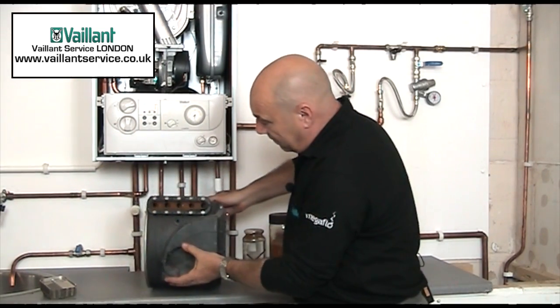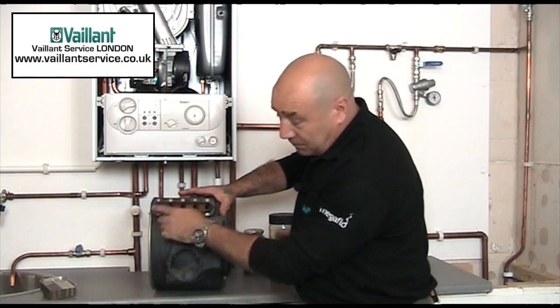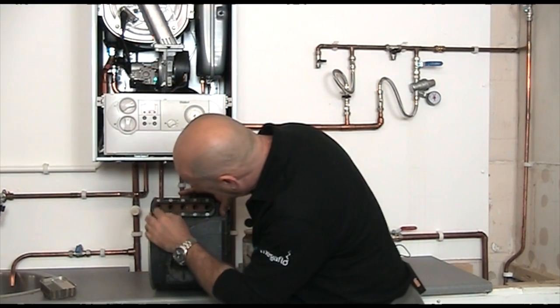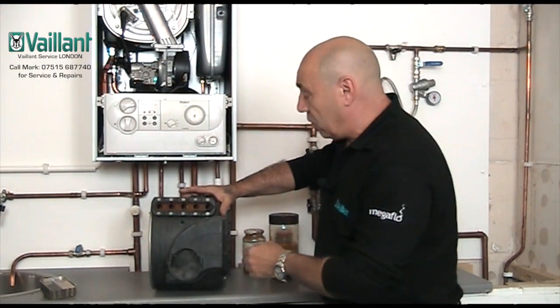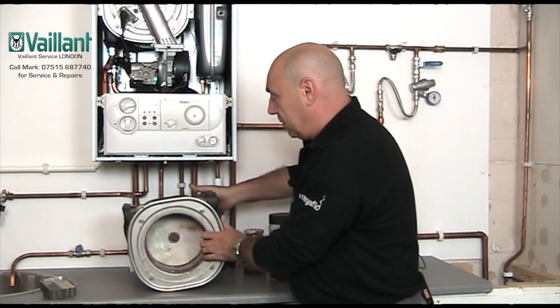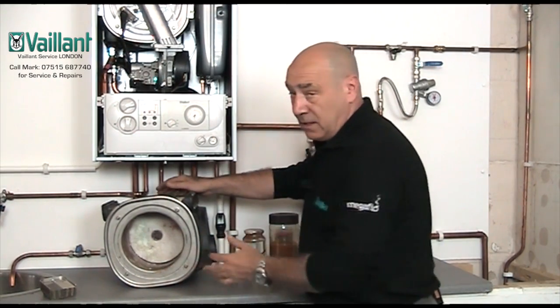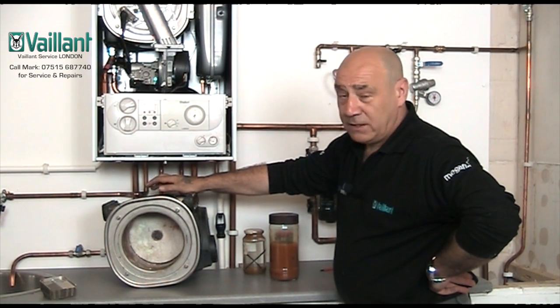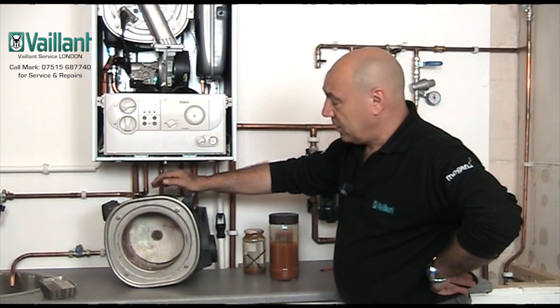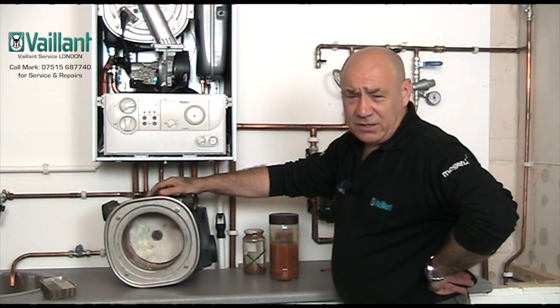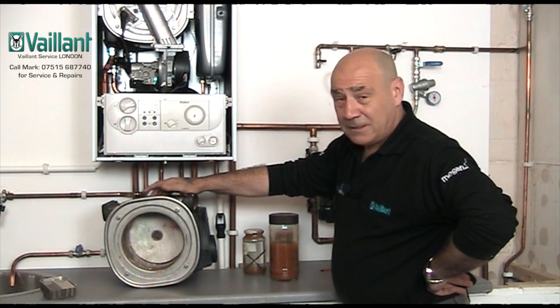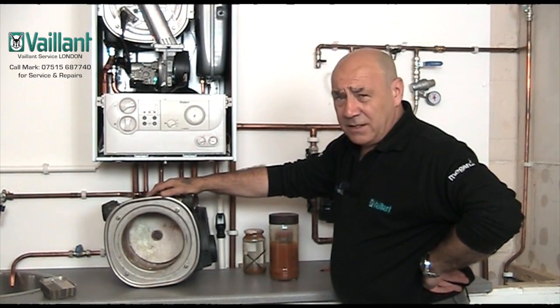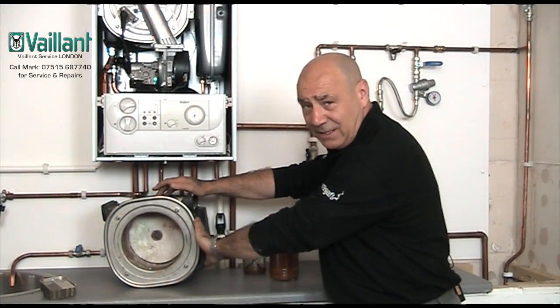You might think it'd be easy to pump it out or clean it — the answer is no, it's not. Very difficult to clear and clean. Generally speaking, if the heat exchanger gets into that sort of condition, you're looking at writing the boiler off. These heat exchangers cost anything from £400 to £600 or £700 just to purchase. So if this gets blocked up, you pretty much kiss goodbye — it's all over, get rid of your boiler, it's a write-off. Very important that you do not put anything into this that shouldn't be in there.